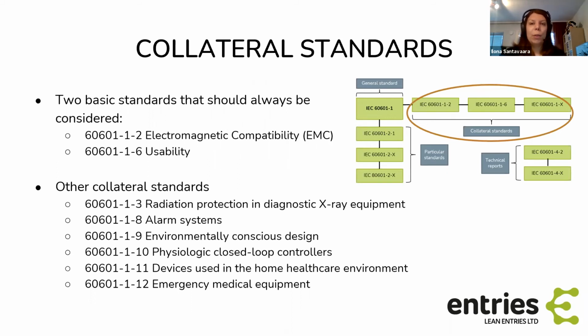And then about collateral standards. Basically there are two very basic standards that should pretty much always be considered. If it's an electrical medical device, you will most likely have to consider electromagnetic compatibility, so EMC. That is such a big thing that I have dedicated a couple of slides at the end of this presentation to that topic. But the other one is usability. That is -6 of the collateral standards. And I think we already had the usability session. As was stated there, this standard doesn't have much content, so it mostly refers to 62366, which is the main usability engineering standard. But in any case, this applies to your device.